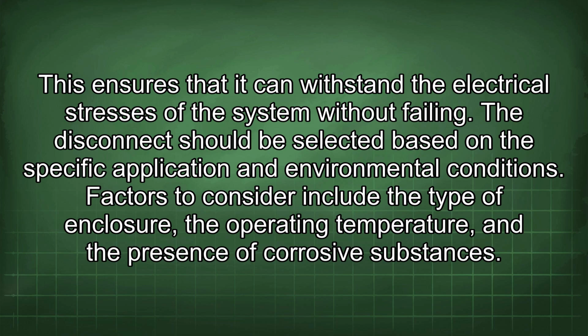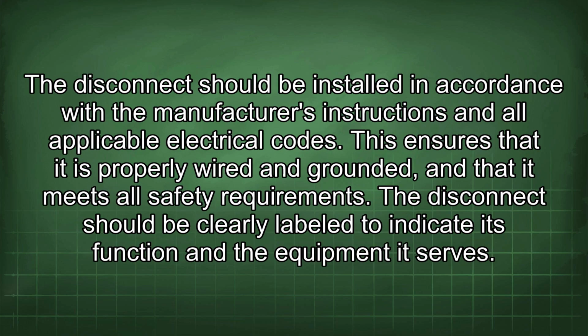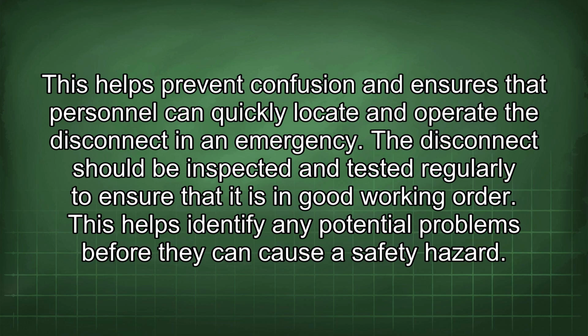Factors to consider include the type of enclosure, the operating temperature, and the presence of corrosive substances. The disconnect should be installed in accordance with the manufacturer's instructions and all applicable electrical codes. This ensures that it is properly wired and grounded, and that it meets all safety requirements. The disconnect should be clearly labeled to indicate its function and the equipment it serves. This helps prevent confusion and ensures that personnel can quickly locate and operate the disconnect in an emergency.